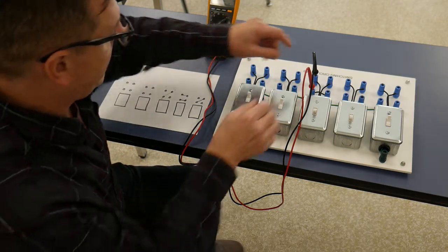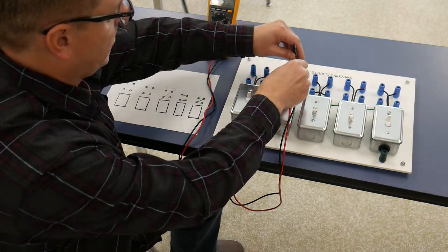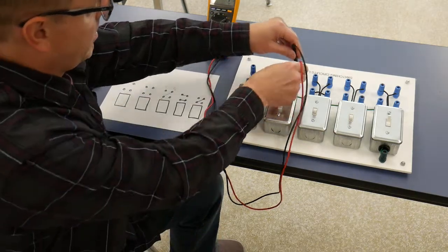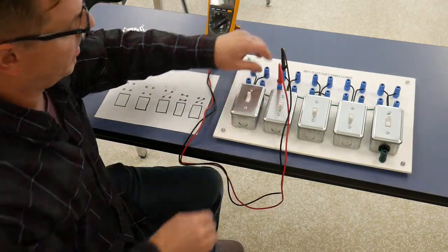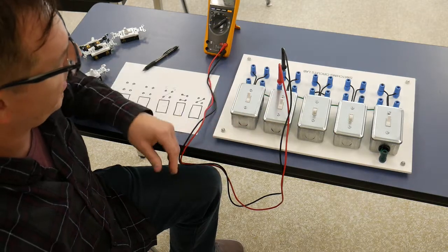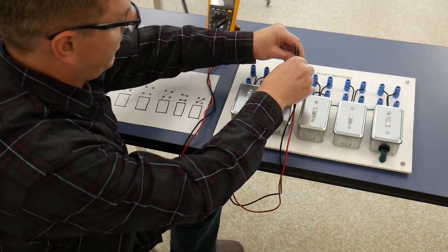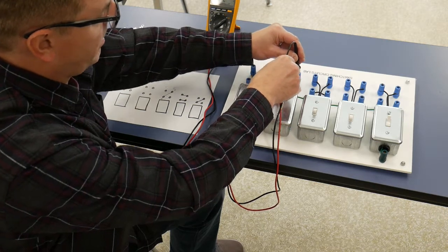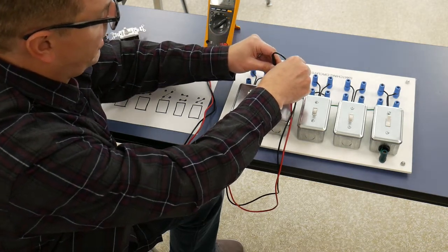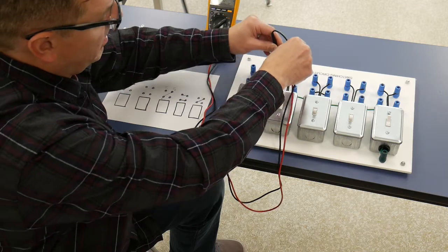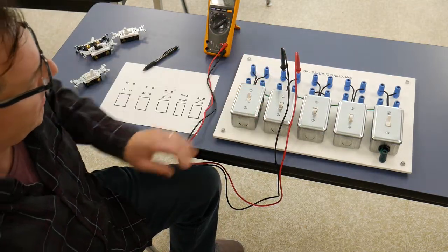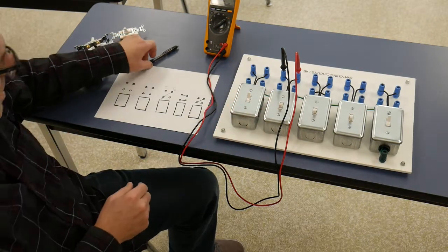I'm going to label those as. Okay, next switch over. We're going to come to this guy. We got a beep top to bottom. This should also beep top to bottom, which it does. Turn it the other way, we get nothing and nothing. Go crisscross, crisscross, nothing. Side to side, we've got a beep there, and we then have a beep there. So that tells me that this is my 4-way switch.